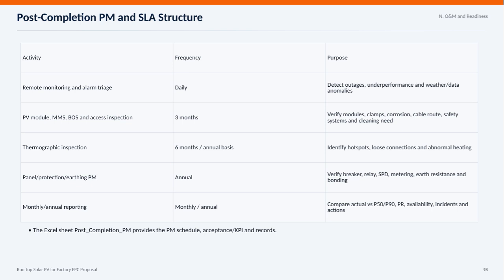Every 3 months, thorough inspections cover the PV modules, mounting systems, cables, and safety elements to catch any corrosion or needed cleaning. Thermographic inspections are carried out semi-annually or annually to identify hotspots or any abnormal heating that could signal potential failures. Annual preventive maintenance includes checking critical protection components like breakers, relays, surge protectors, and grounding systems to guarantee safety and reliability. Finally, monthly and annual reports compare actual system performance against expected benchmarks like P50 and P90, tracking performance ratio, availability, and any incidents or corrective actions taken.